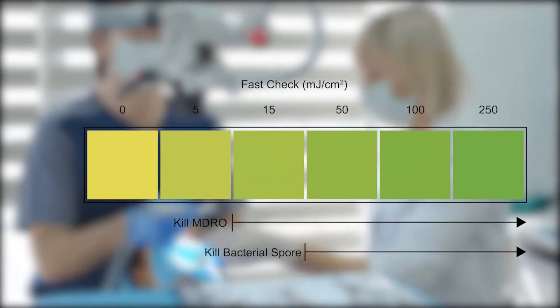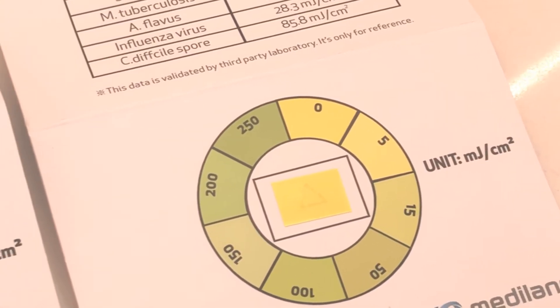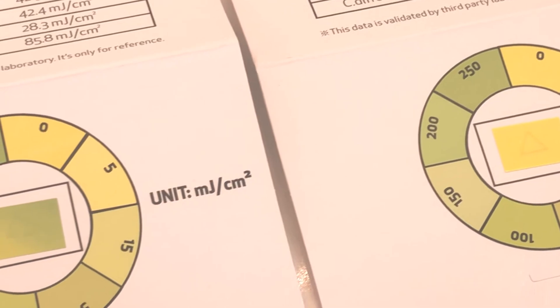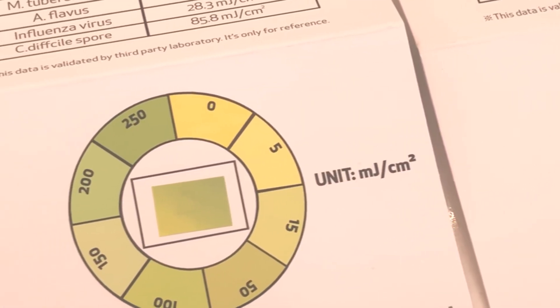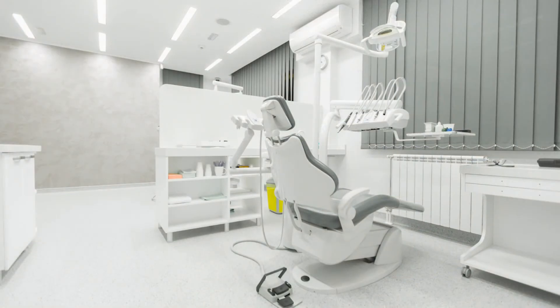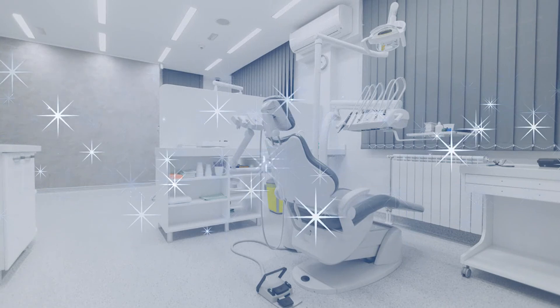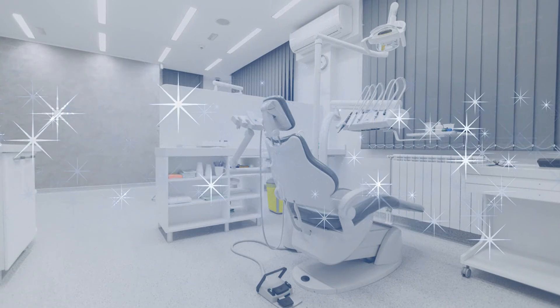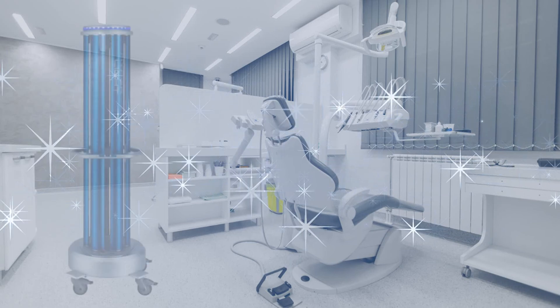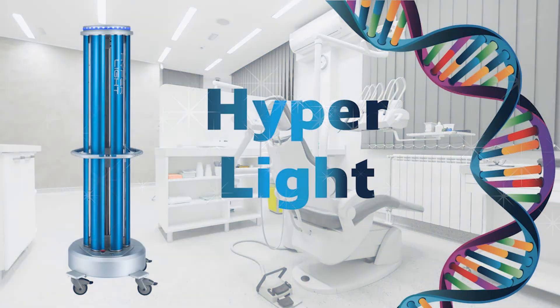An operation of only 5 minutes will result in the elimination of more than 99.99% of the microorganisms in the room. An examination of the control card placed ahead of time will show us the radiation efficiency. This way, in just a few minutes between patients, we can make sure that the operation room is disinfected in the most effective way — not by surface disinfection that might miss certain areas, or by air filtration that does not affect the surfaces. Hyper Light: the disinfecting robot that microorganisms cannot hide from.